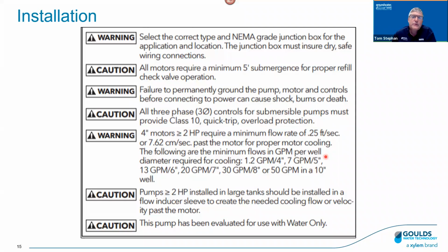The next bullet here really just talks about cooling. And anytime you look at an installation manual with a motor, that motor manufacturer is going to have some specs regarding, you know, the number of starts or something related to cooling, because cooling is a big issue with motors, right? So when you start a motor in, let's say, a fixed speed application, you give it a lot of amperage, right? And amperage is heat. So now you have to dissipate that heat somehow. So that's always a concern from the motor manufacturers.